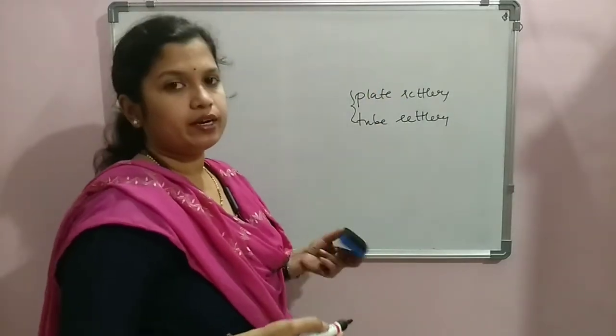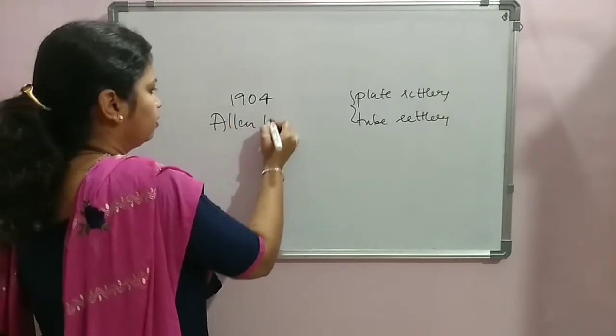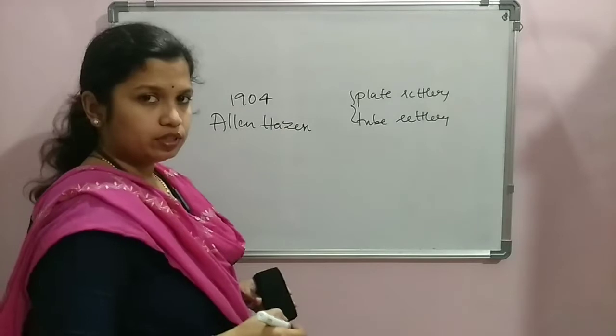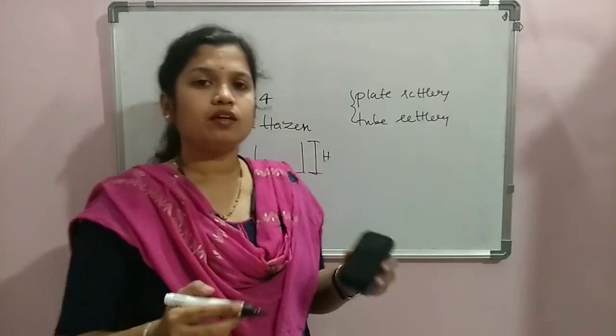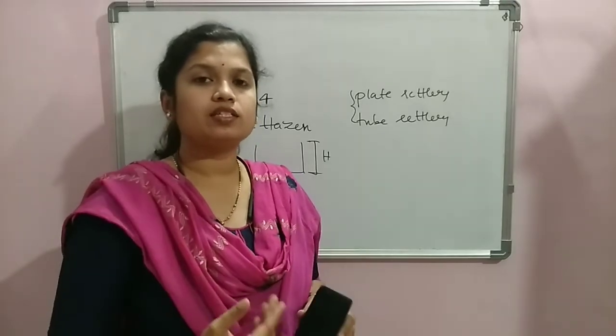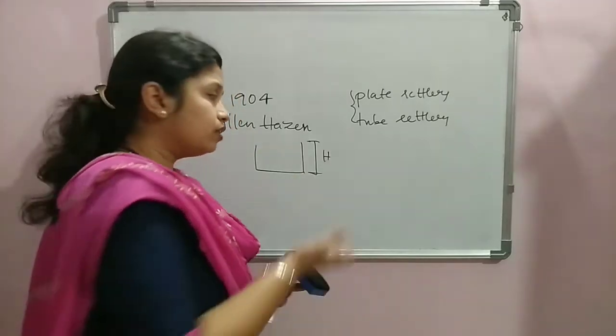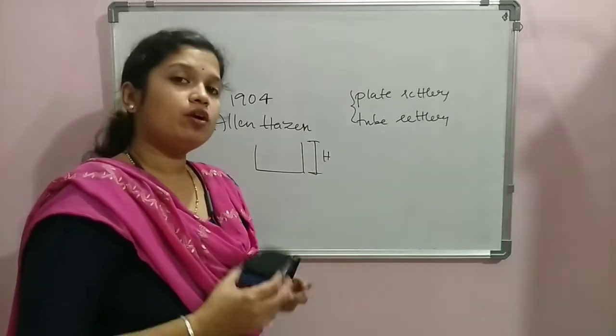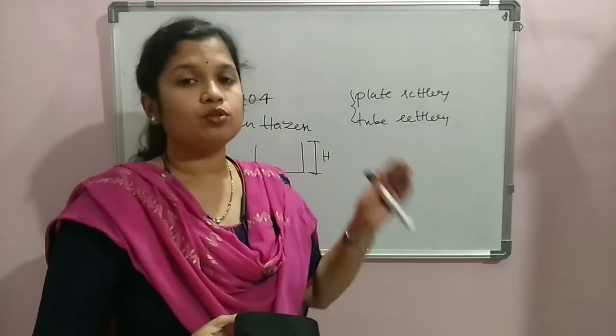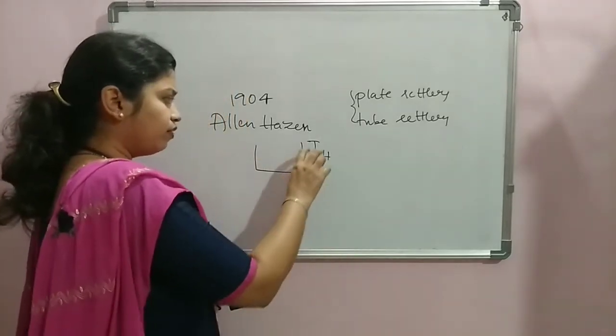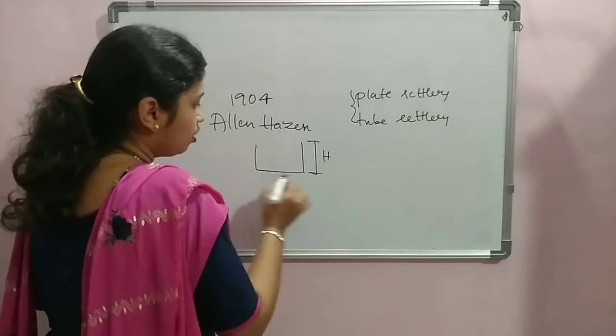In 1904, scientist Allen Hazen proposed that if we decrease the depth of a sedimentation tank, we can achieve good economy by saving area and achieve easier sedimentation, since reducing the depth means particles travel a shorter distance to settle. However, in a typical sedimentation tank we must increase area to slow velocity, so when we decrease depth we must instead increase the contact area.